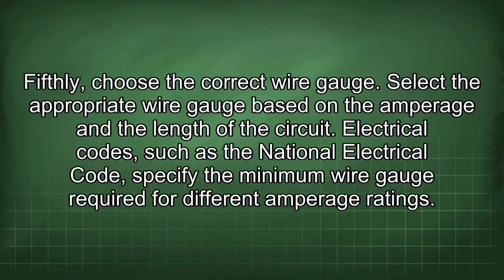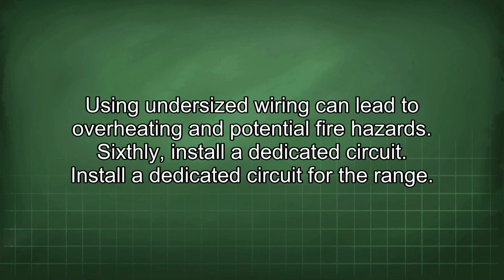Fifthly, choose the correct wire gauge. Select the appropriate wire gauge based on the amperage and the length of the circuit. Electrical codes, such as the National Electrical Code, specify the minimum wire gauge required for different amperage ratings. Using undersized wiring can lead to overheating and potential fire hazards.